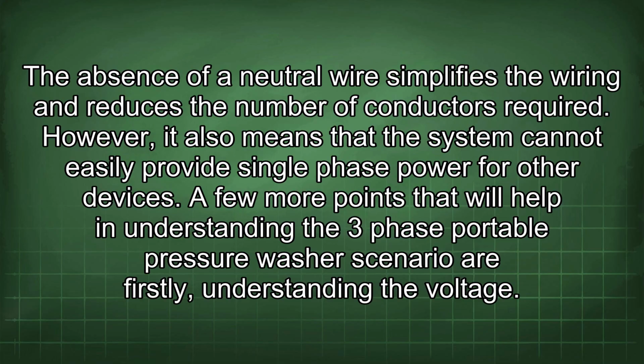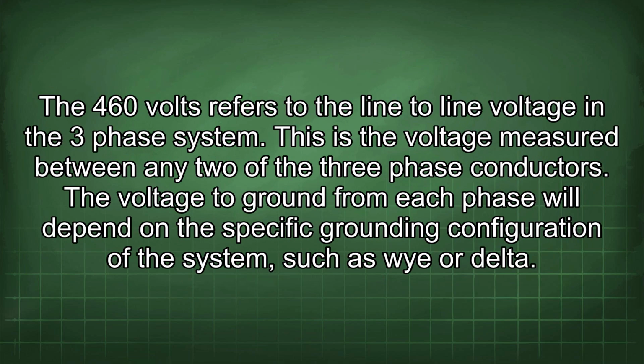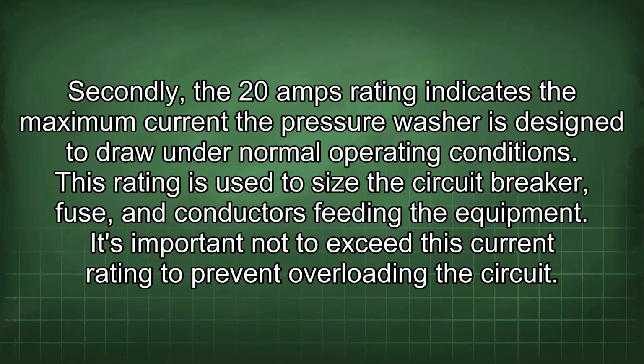A few more points that will help in understanding the three-phase portable pressure washer scenario are: firstly, understanding the voltage. The 460 volts refers to the line-to-line voltage in the three-phase system. This is the voltage measured between any two of the three-phase conductors. The voltage to ground from each phase will depend on the specific grounding configuration of the system, such as Y or delta. Secondly, the 20 amps rating indicates the maximum current a pressure washer is designed to draw under normal operating conditions. This rating is used to size the circuit breaker, fuse, and conductors feeding the equipment. It's important not to exceed this current rating to prevent overloading the circuit.